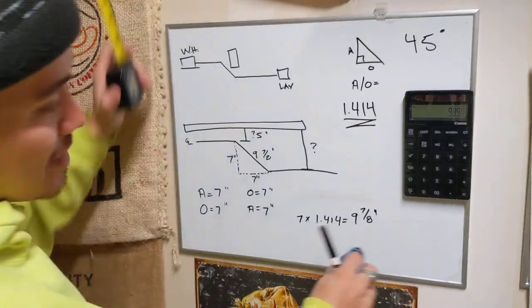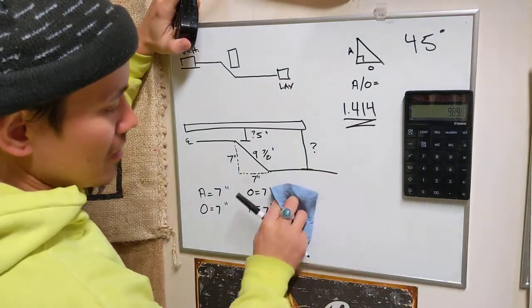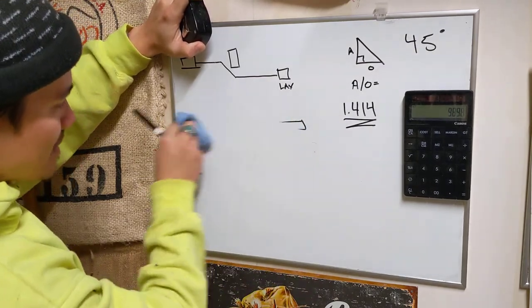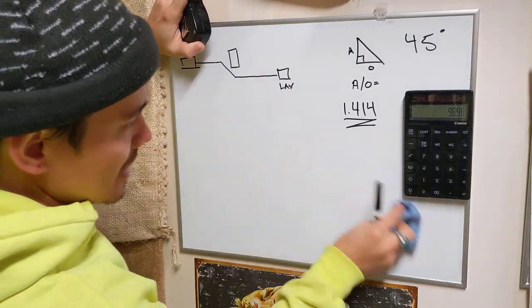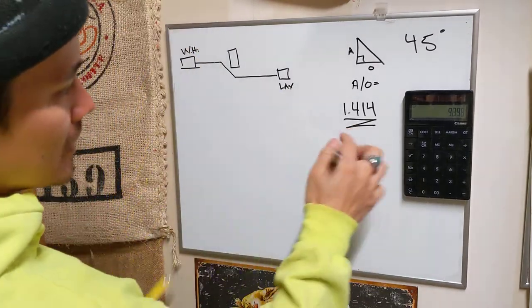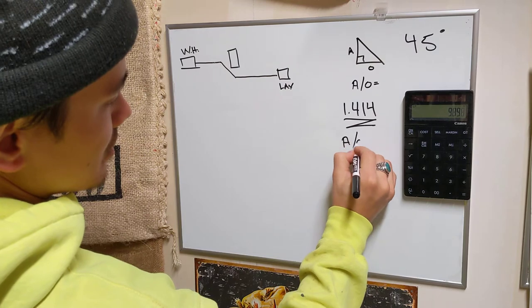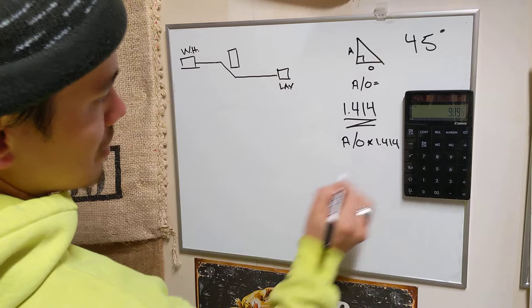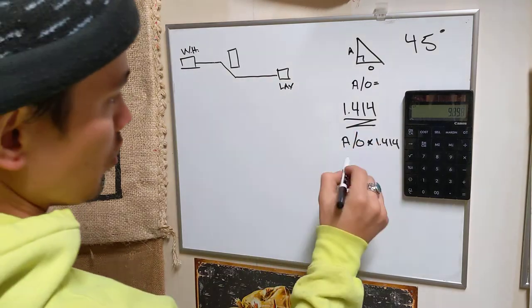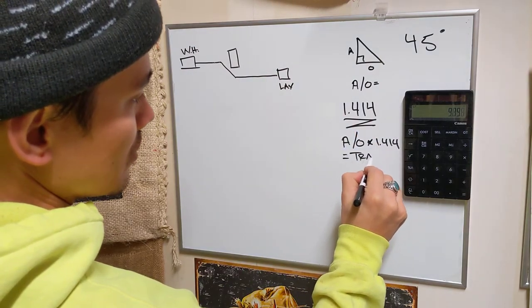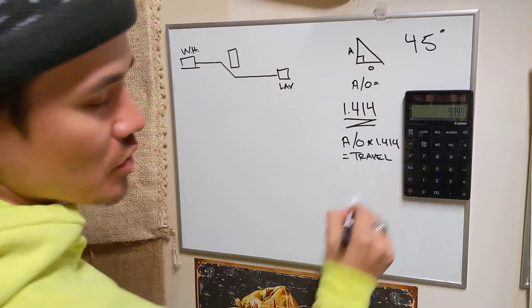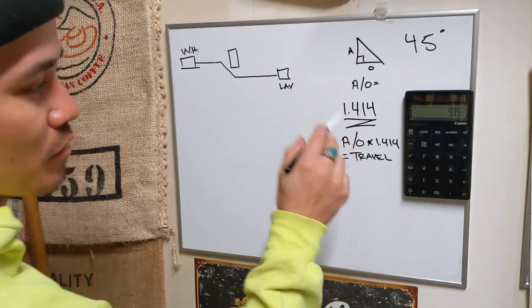Now, the next step, that's not your cut piece. Now, a lot of people forget that last step. And there's one last special. That's how you get your offset is that 1.414. Your advance, your offset times 1.414. It's always going to give you your travel. Always. Advance equals offset. Offset equals advance. 1.414. Repeat that in your head. Memorize it.